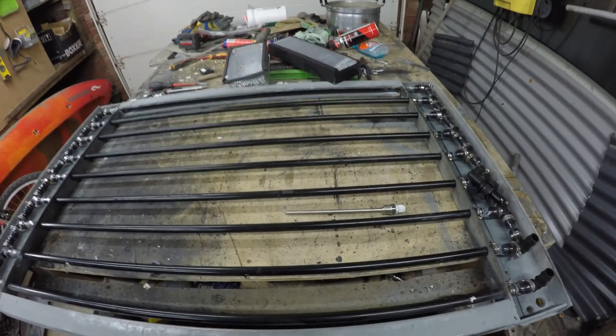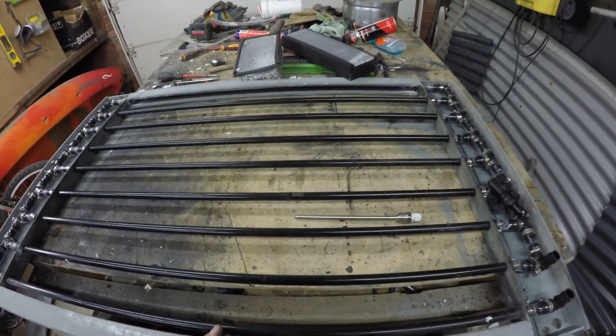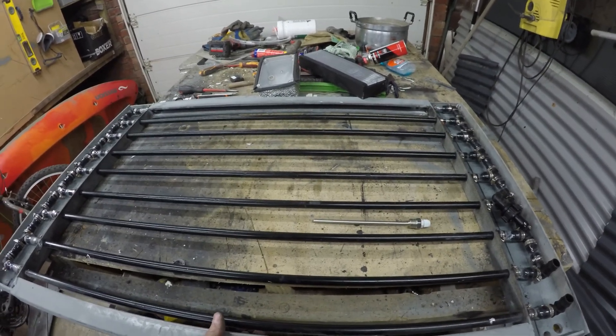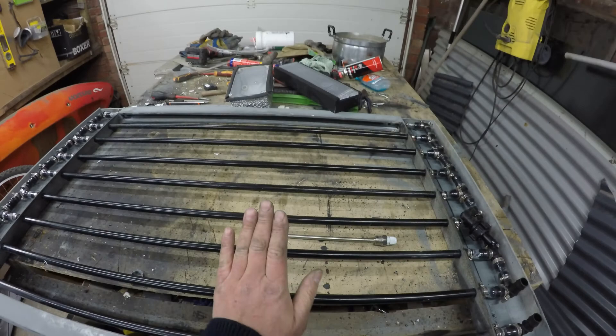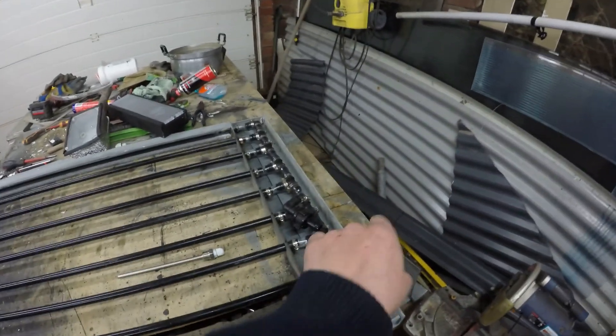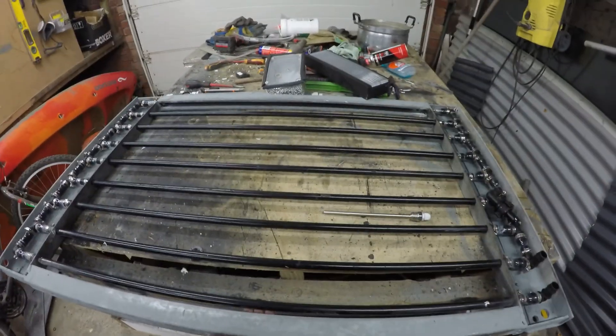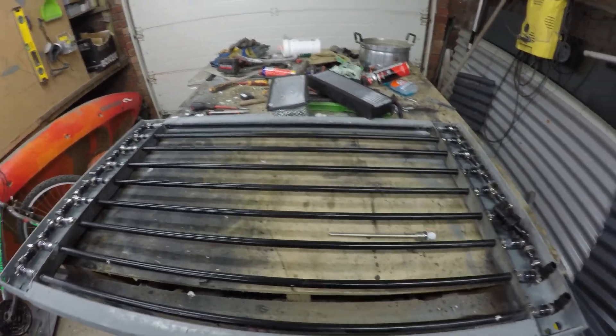Being parallel, I'll have to make sure this is always slanted. It can go horizontal or vertical, but I just have to make sure that if I go horizontal I don't slant it up the wrong way. Because if I do that, the water's going to come in and it's only going to go through the bottom pipes mostly and come out. So ideally I want to have it on a bit of an angle.